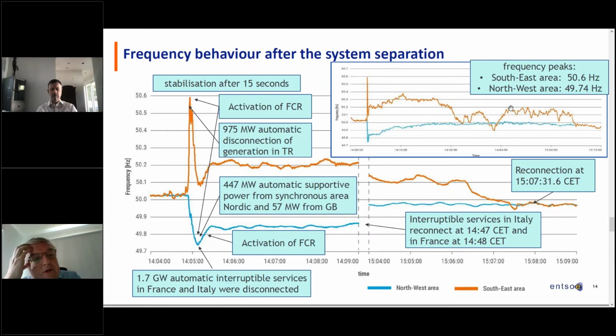So afterwards, what do we see? Well, we see in the Balkan area, which is on the top right, stabilization after 15 seconds, thanks to the activation of frequency containment reserves, and also 975 megawatts of automatic disconnection of generation, which also helped a lot to make the frequency not go up too high. Because there is indeed a risk that the frequency would go too high, and then all generation would disconnect from the grid, and again you would have a blackout.